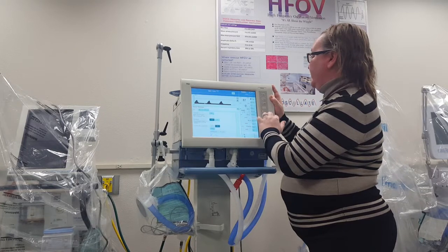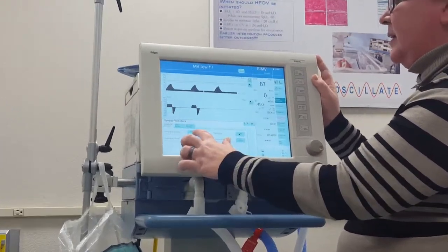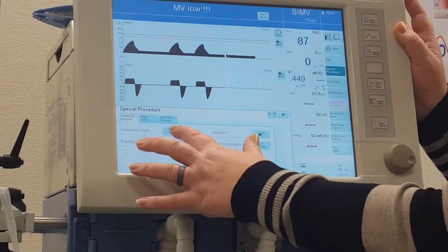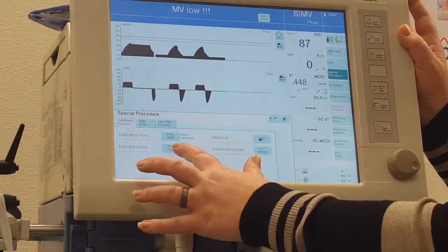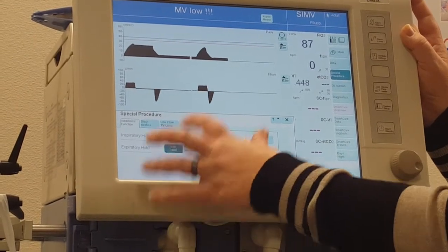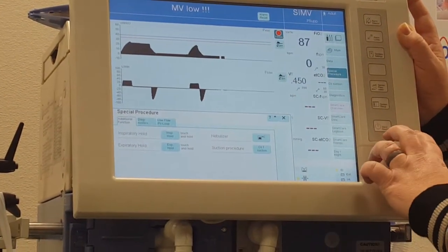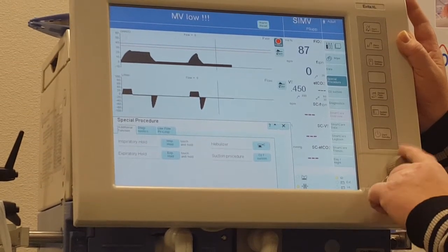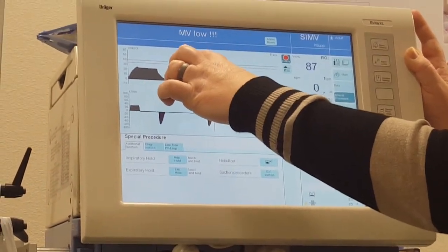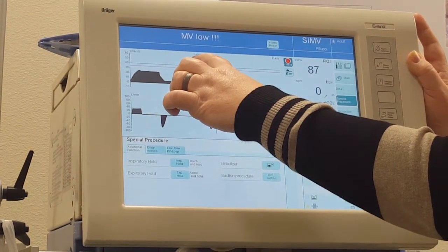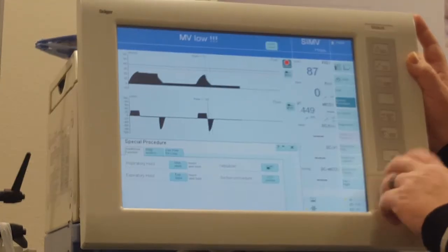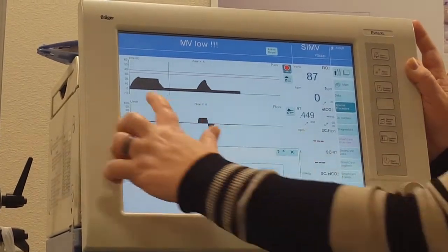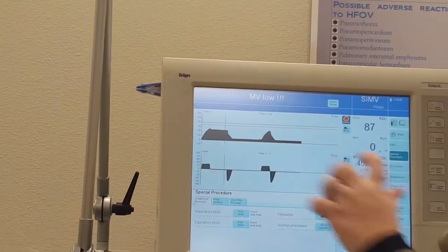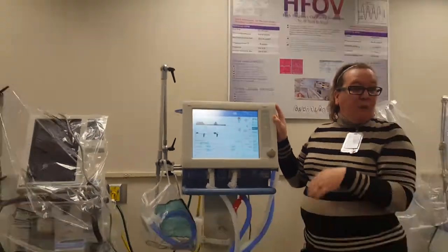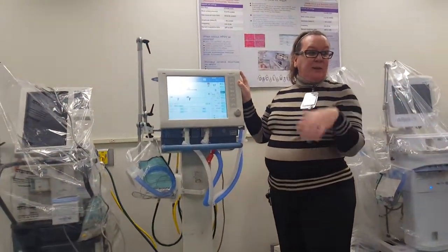Sorry, I'm in the wrong spot. Special procedure. Inspiratory hold. Expiratory hold. Freeze. And then dial over. See, the DRAGER tends to put paw for everything, and that's why I want you to know that that's not mean airway pressure. That's their way to say regular pressure. So that's where you get plateau. But you have to go all the way over to where the flat part is. Right there, that's where you get the plateau. Does that make sense? Paw on the DRAGER just means pressure, where in any other vent it means mean airway pressure.